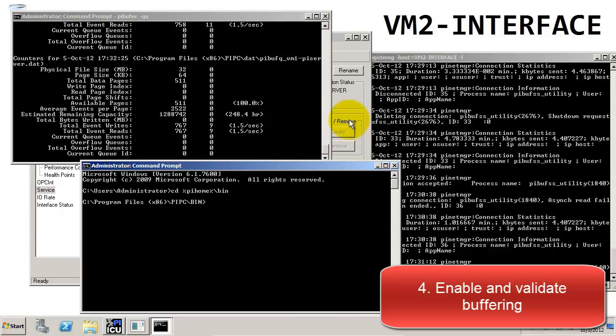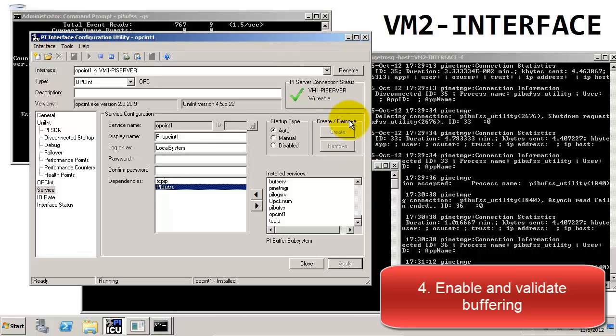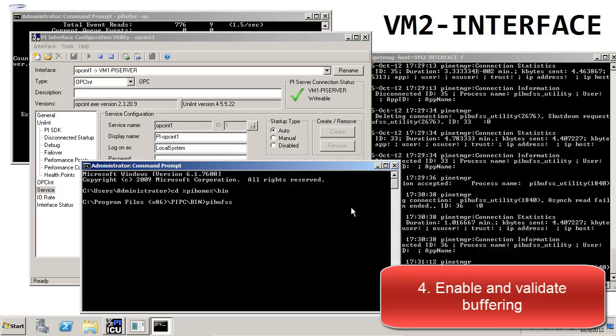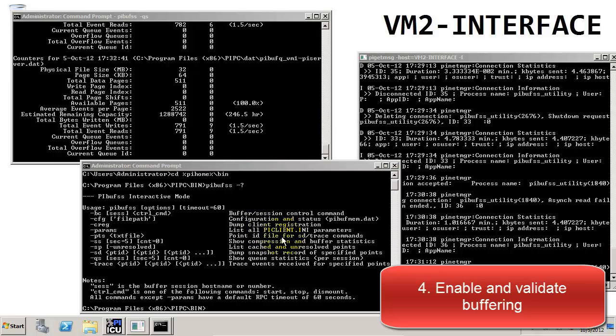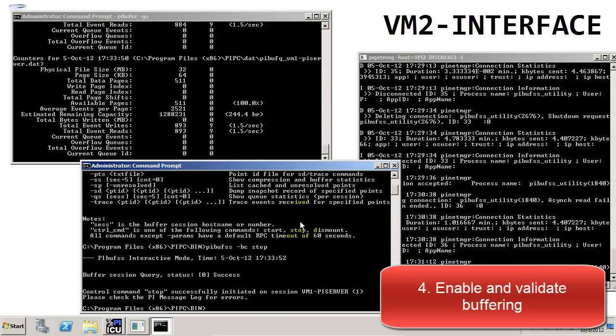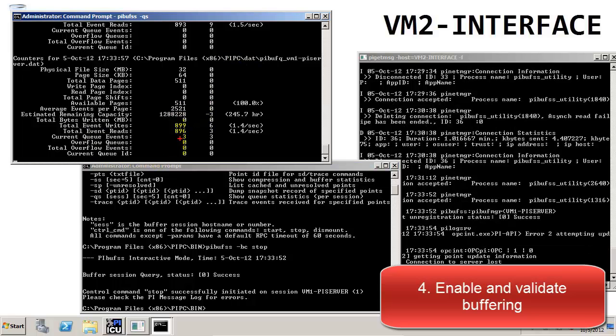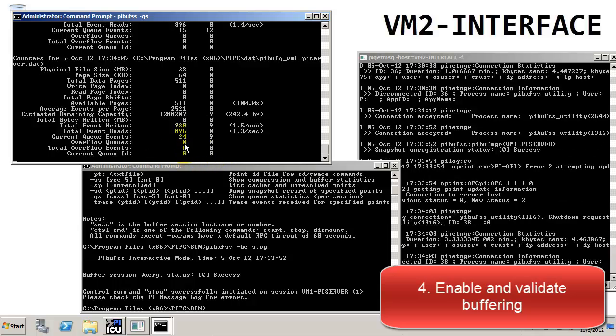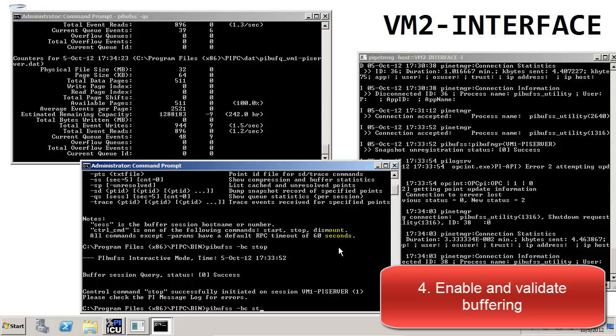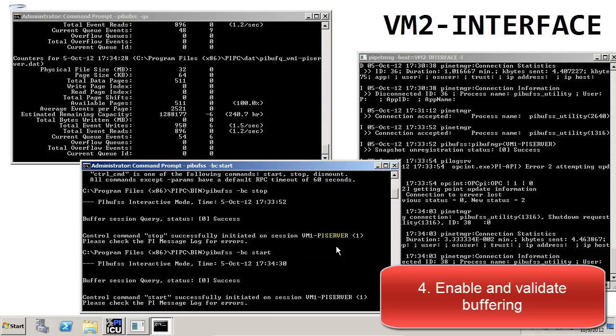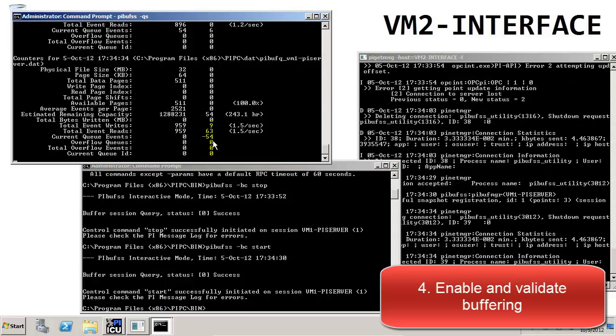If we want to see what happens when the PI Buff SS loses connection with the PI Server, we can use PI Buff SS with a different parameter. Going back to the question mark list, we see there's a dash BC. We will use dash BC stop to simulate a disconnect from the PI Server, and then take another look at the queue statistics. Back in the queue statistics, we notice that current queue events is no longer zero — there's a three, which means events are building up in the queue. This is expected since we've lost connection with the PI Server and data is now being buffered. If we go back to PI Buff SS dash BC and type in start instead of stop, we will regain the connection to the PI Server. Going back to the queue statistics, we can see that it flushes almost immediately and there are no longer any queued events.